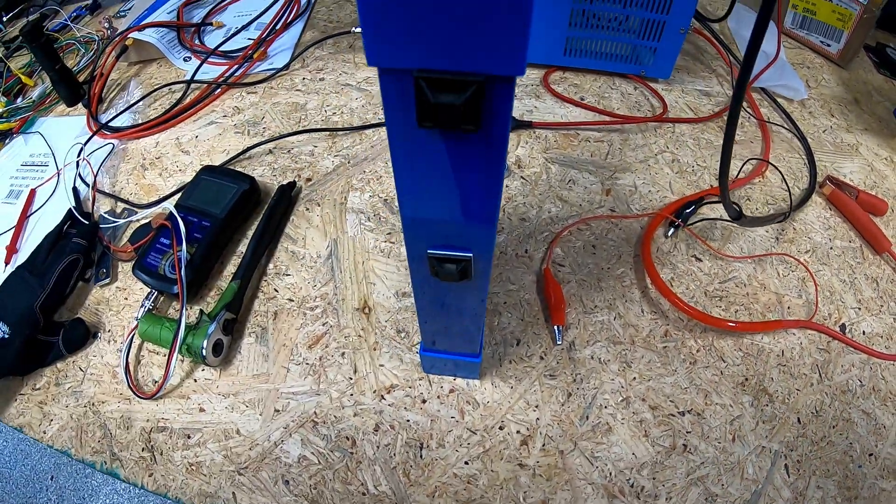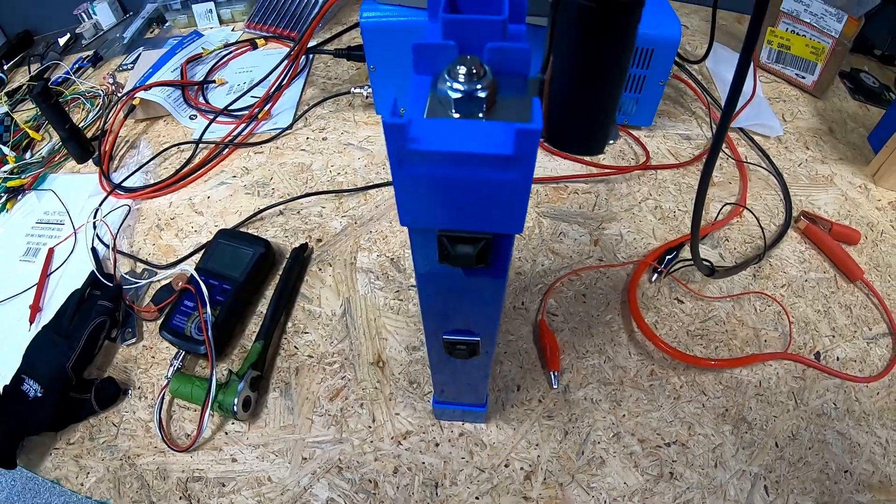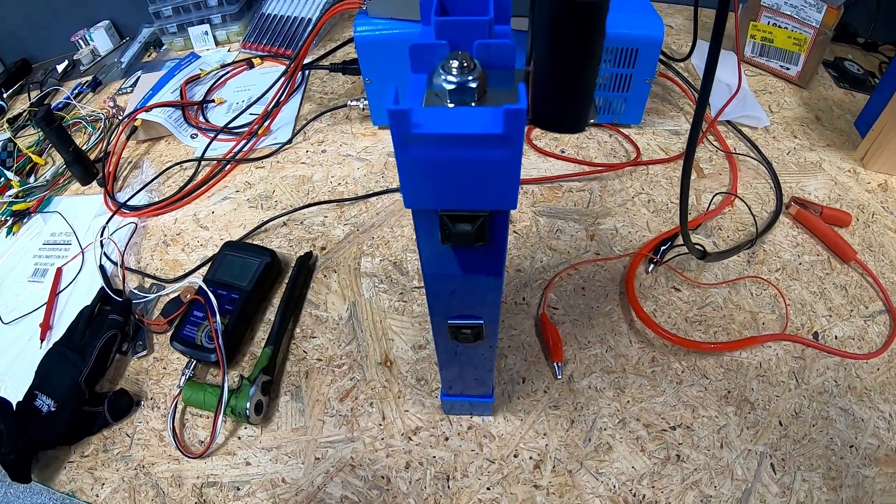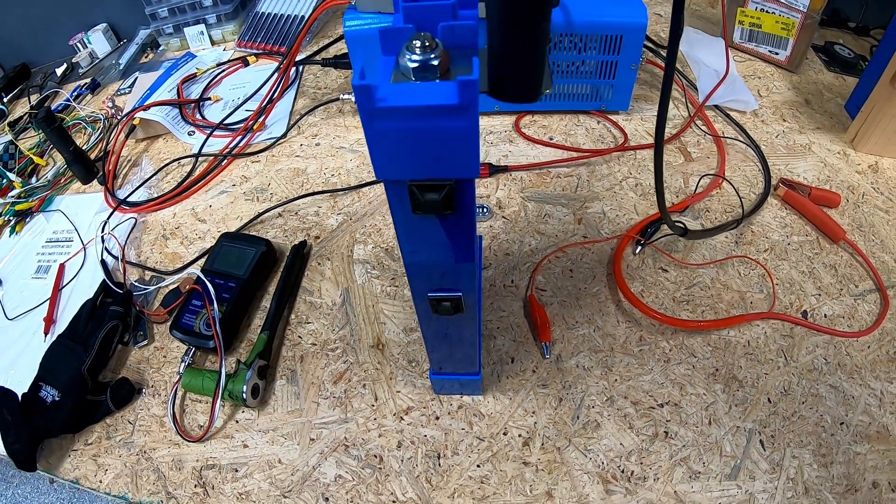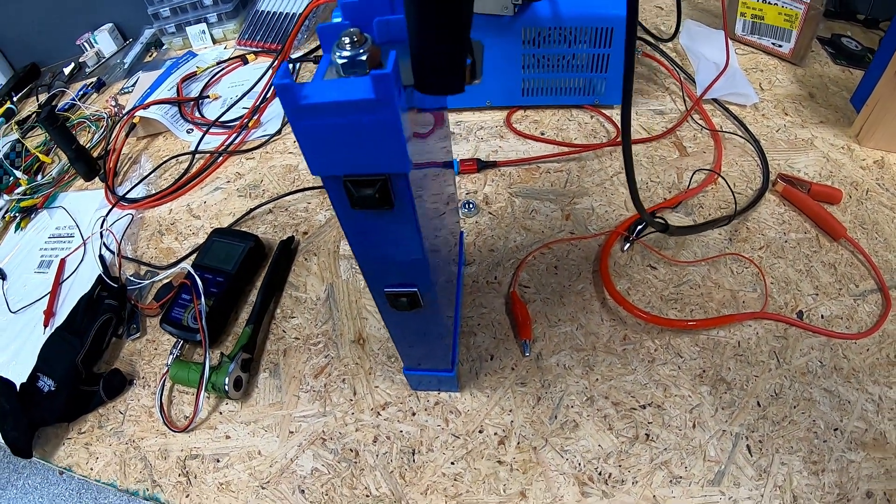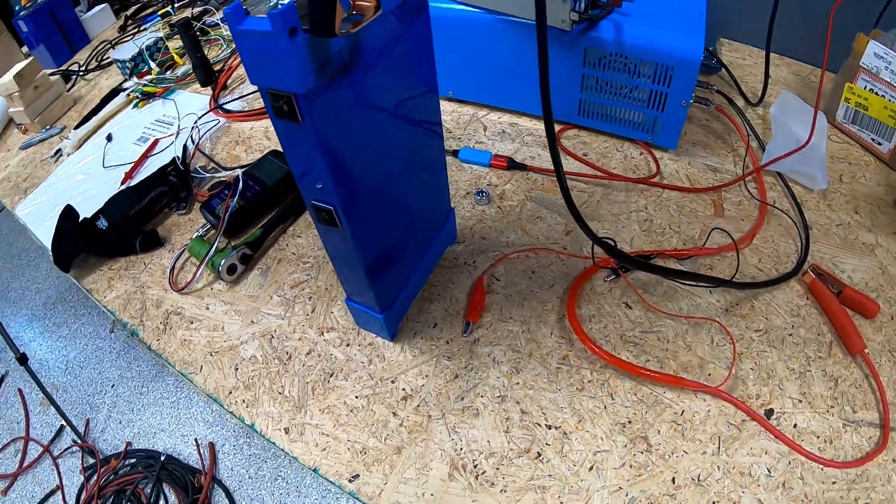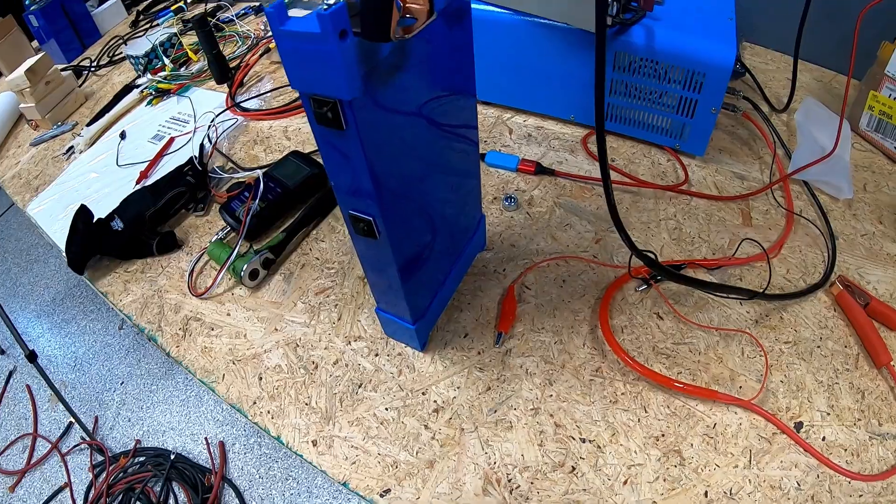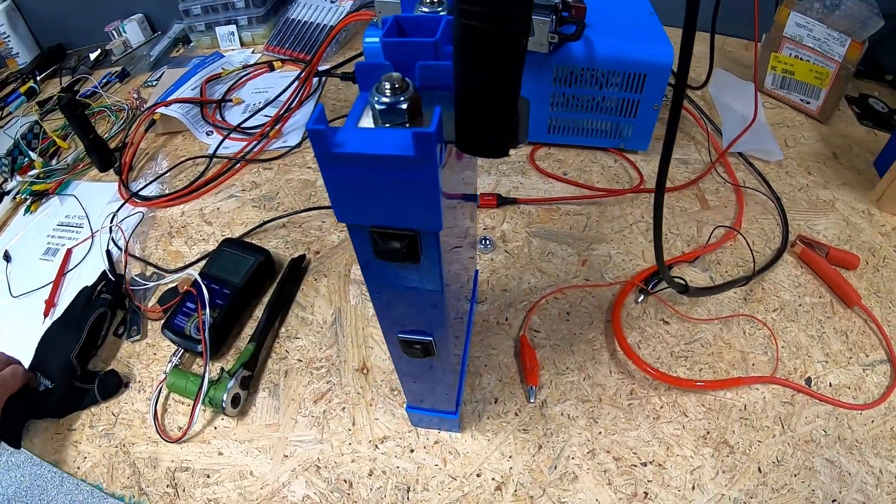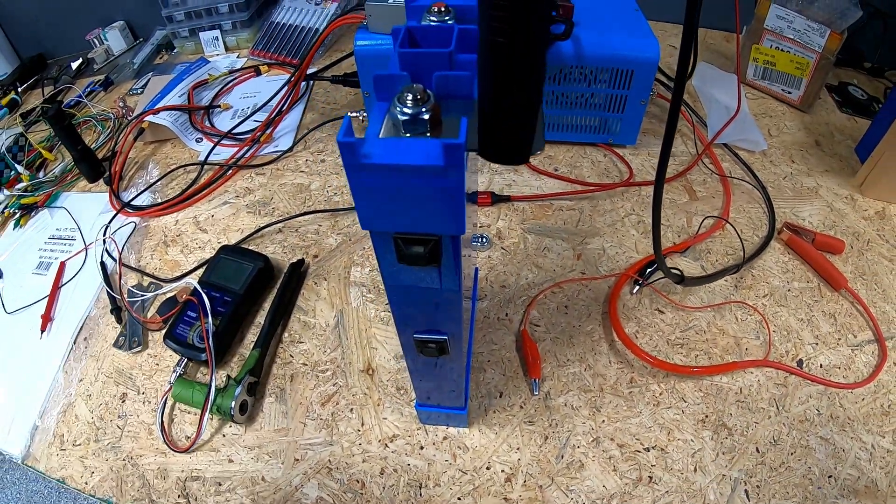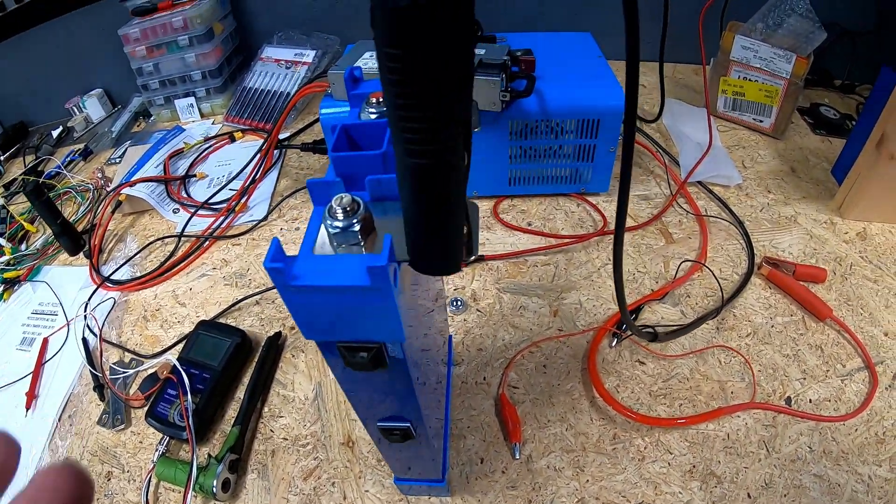So it looks like we are at 0.61 milliohms, as you can see there, at 3.29 volts. So 0.61 milliohms, and that is with the battery at its current state of charge. What I will do is I will look up the specs on this battery and pull them down and see what it was originally.